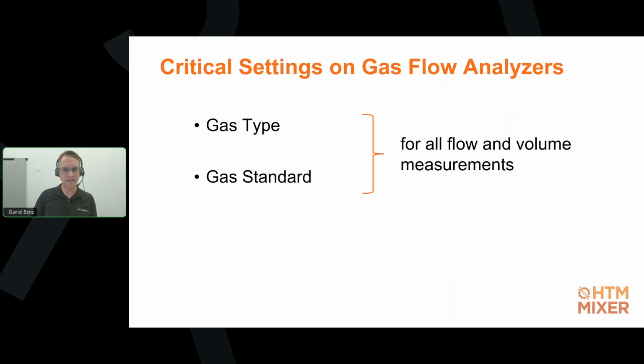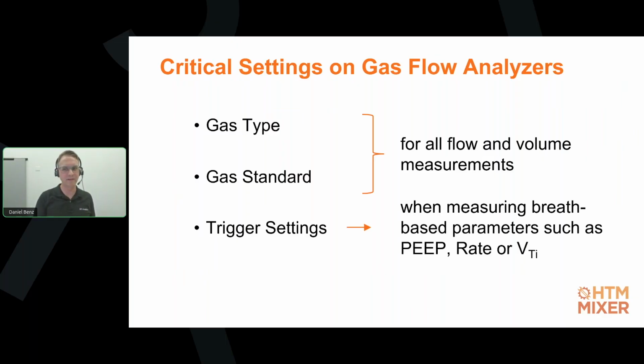The third setting we are going to talk about is actually a set of settings. It's the trigger settings. They are relevant when we want to measure so-called breath-based parameters, such as, for example, PEEP pressure, respiratory rate, or tidal volume. And last but not least, the measurement parameters themselves. Gas flow analyzers can measure many different parameters in different units of measurement. So we must ensure that we look at the right parameter and have it set up with the correct unit of measure.